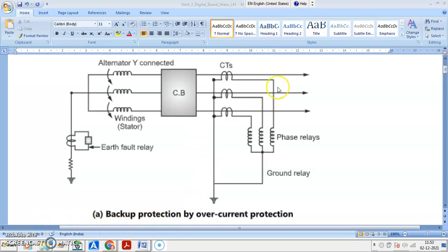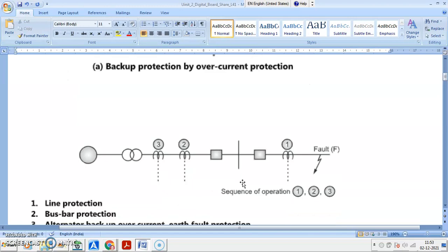Backup protection is provided by the adjacent protection zone protective system. म्हणजे त्याच्यामध्ये इकडे येईल busbar protection आणि इकडे येईल earth fault protection. So this is busbar protection that is provided, earth fault protection is provided. पुढच्या डायग्राम मध्ये we have explained this.